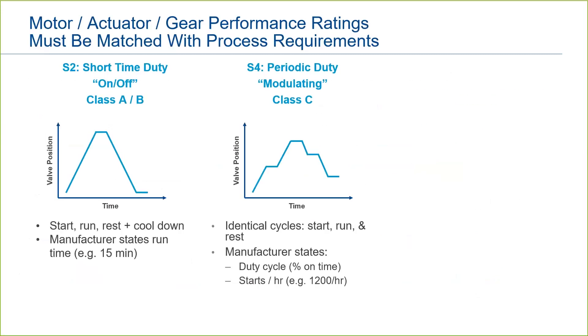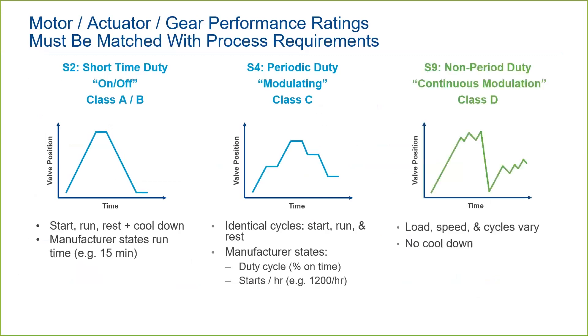The third rating is S9 non-periodic duty, also called continuous modulation or class D. Here, basically anything goes. The load, speed, and cycles can vary. Also, there are no requirements to have a period of rest or cool down, so the motor must be able to move continuously.